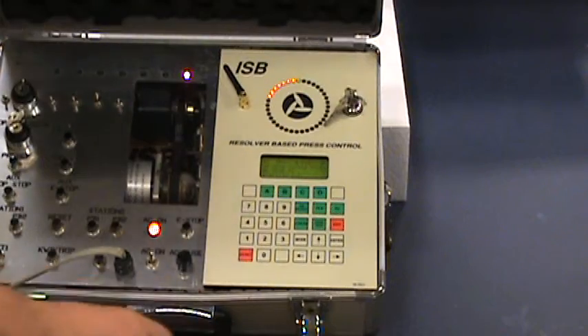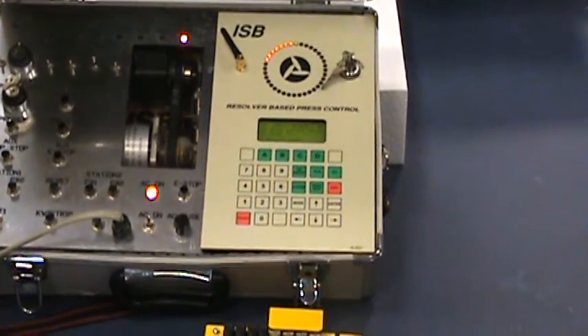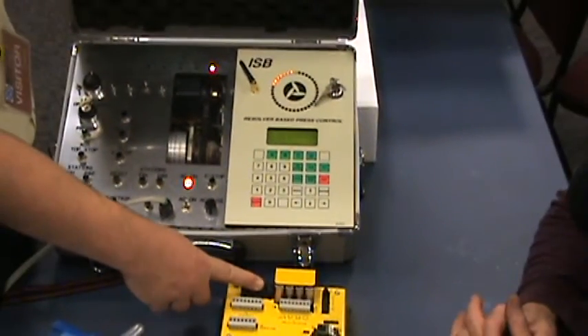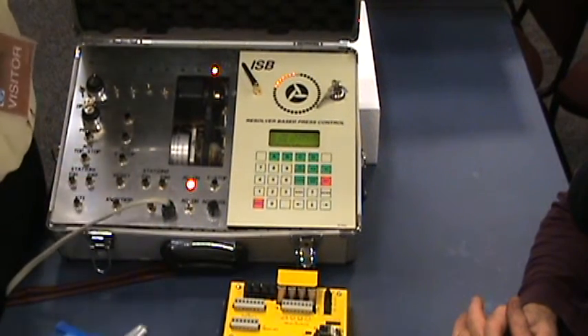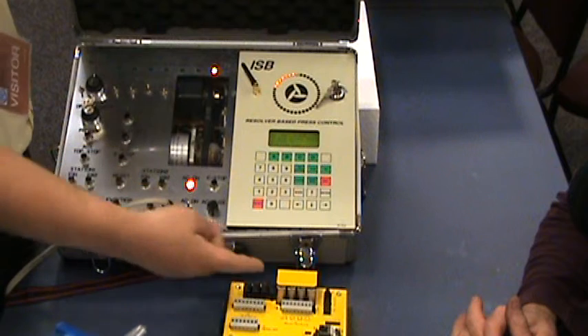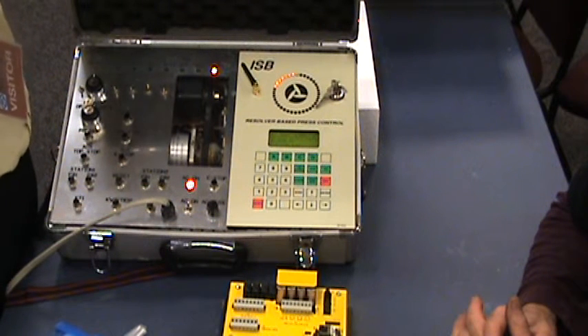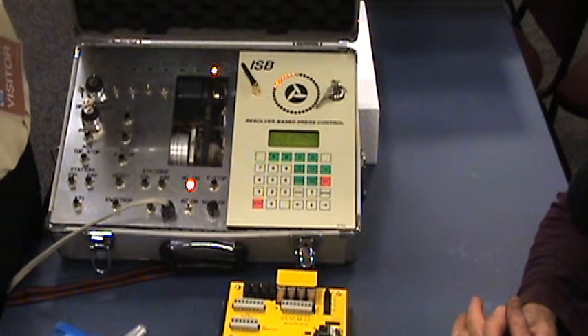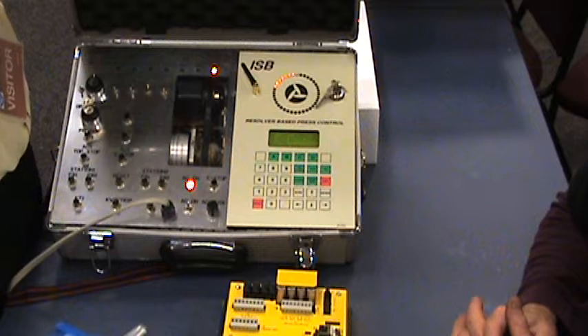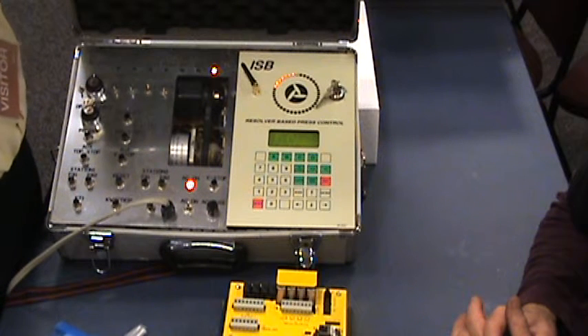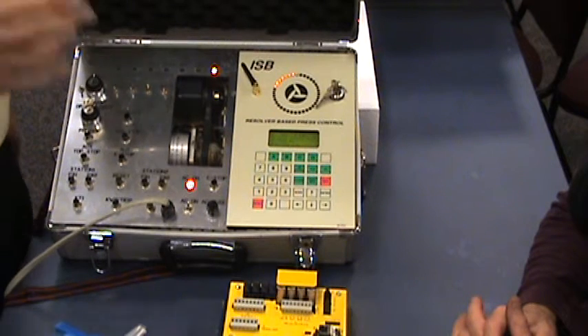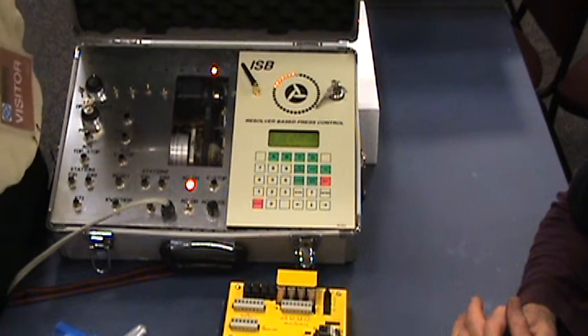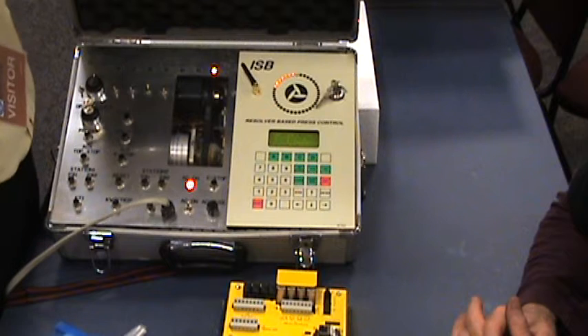Now, these are four small mechanical relays. If you're turning on and off something like a counter or a digital input to a controller, the feed window for a servo feed, these relays will last indefinitely. But any mechanical relay has a finite life. And the more of a load you run through it, the life is inversely proportional. In other words, the more load you run, the shorter the number of cycles that it can turn on and off that load before it corrodes and pits the contacts.